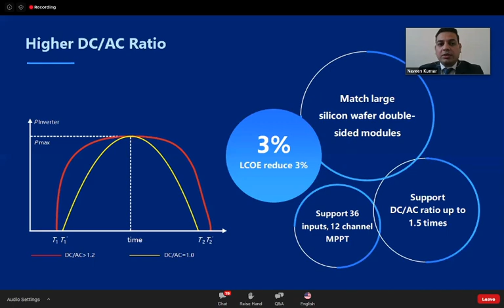In that way, we are not utilizing the inverter to its fullest capacity. But in the red curve, when the DC-AC ratio is increased to more than 1.2, you can see the curve is extended, meaning the generation is extended. You are able to get maximum output from your fixed PV asset. And the PV technology is also changing: bifacial module systems, and module capacity has increased to 440, and now people are talking about 500 watt peak also. Our inverters are capable of handling these PV modules. The inverter can support higher DC-AC ratios, and it has 12 MPPT channels, which can support 36 DC inputs.